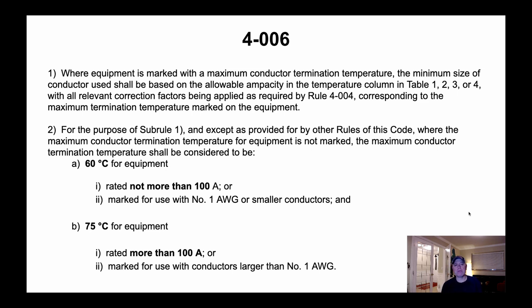It says here: where equipment is marked with the maximum conductor termination temperature, the minimum size of the conductor used shall be based on the allowable ampacity in the temperature columns in Tables 1, 2, 3, or 4 — with all relevant correction factors being applied as required by Rule 4-004 — corresponding to the maximum termination temperature marked on the equipment. That is the one thing I didn't mention.